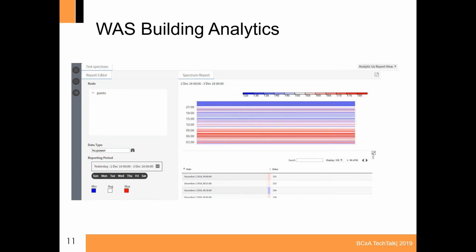Fantastic. I said, show me different ways I can look at this data. And this is probably not the best way to represent it, but it's the way they showed it to me first. And I looked at that for a few moments, and I said, wait a minute, this is Sunday? They said, yes. I said, okay, it's Sunday. Why am I seeing high electrical demand at 3 a.m. on a Sunday morning? They said, oh, they must have overridden the system.